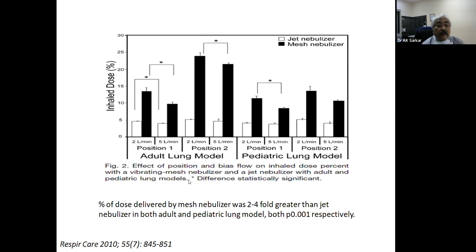This is an interesting slide showing why the jet nebulizer should be used much distal on the inspiratory limb from the Y. This is the ideal position, because if you use the jet nebulizer there, even the drug released during the expiration phase will remain in the inspiratory limb, so it acts as a spacer, and during the next inspiration it will go straight through the endotracheal tube into the patient's lung. So there won't be any loss of drug.